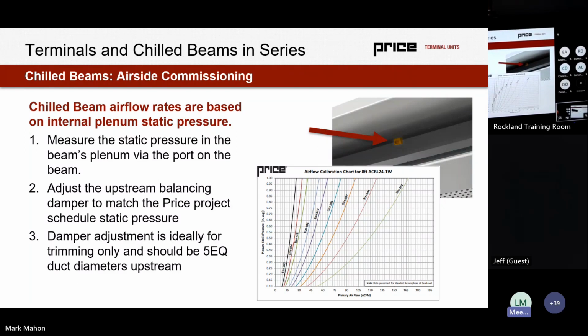And ideally also, and this is just another point, that balancing damper, we generally want it for trimming only, so we don't want it to ramp really low down, mostly because of acoustics. And we want that further away from the beam if possible for acoustical considerations as well.